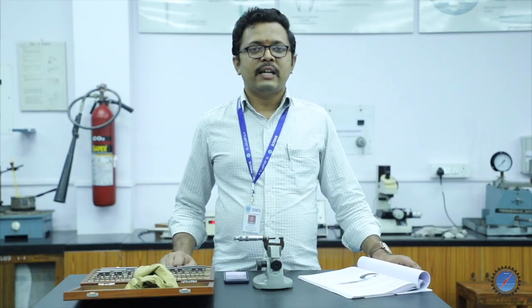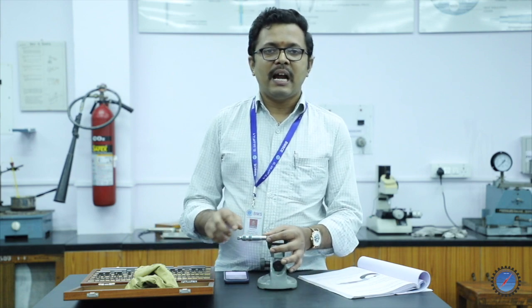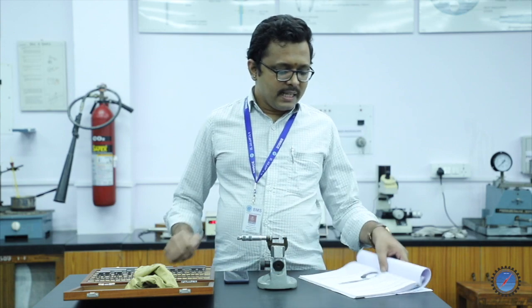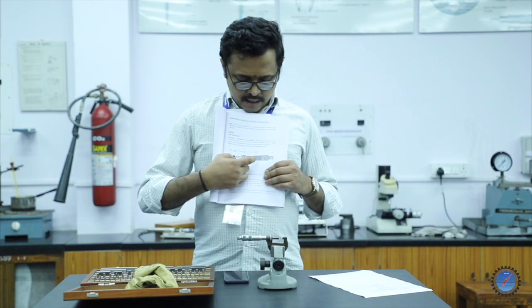We are going to conduct an experiment on calibration of a micrometer. A micrometer or screw caliper works on the principle of screw and nut. We have a main screw that acts like a thimble. We have two types of scales: one is called the main scale (MSD) and the other is the pitch scale (PSD). Whenever an instrument is given to you, you have to find the range and the least count of the system.